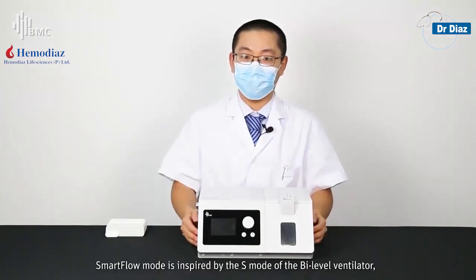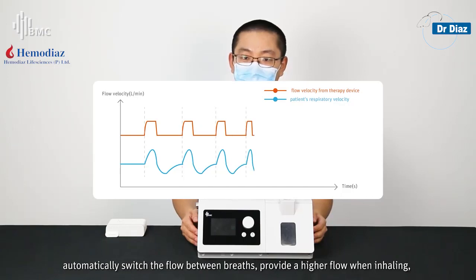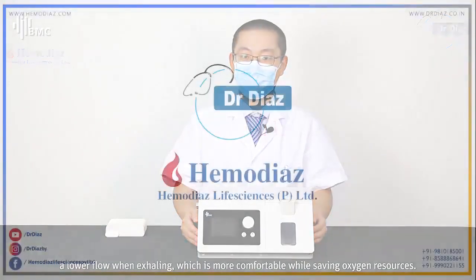Smart Flow Mode is inspired by the S mode of the bi-level ventilator. It can follow the patient's every breath and automatically switch the flow between breaths — providing a higher flow when inhaling and a lower flow when exhaling, which is more comfortable and saves oxygen resources.